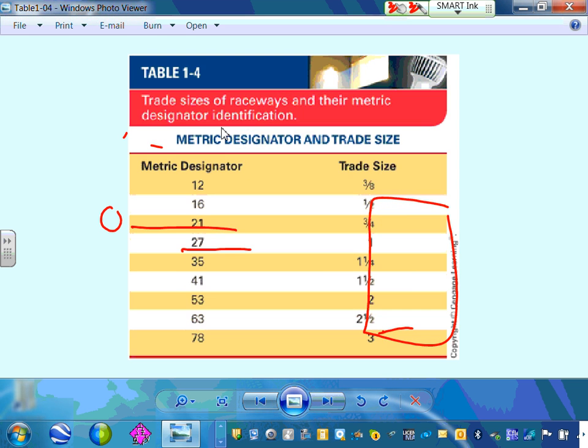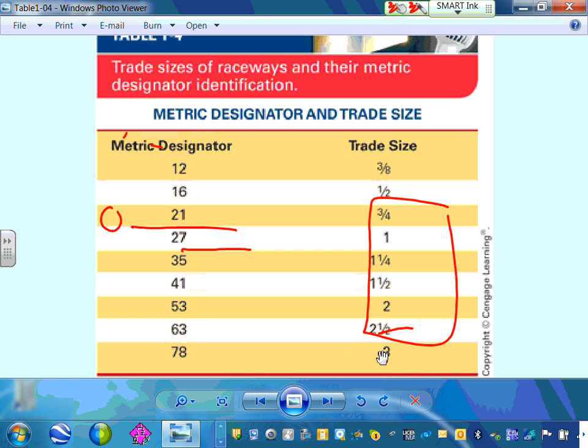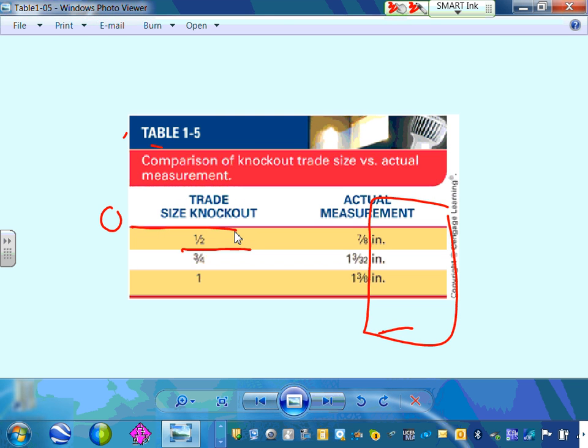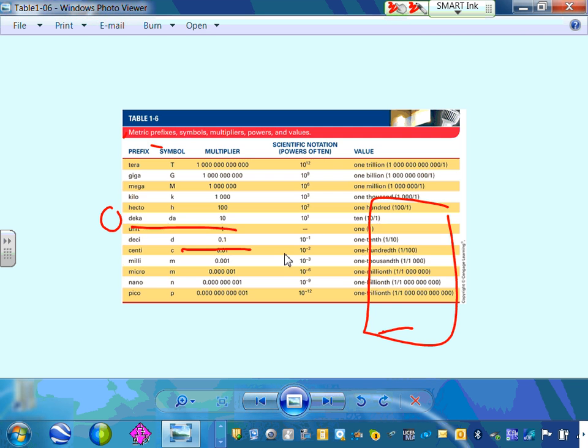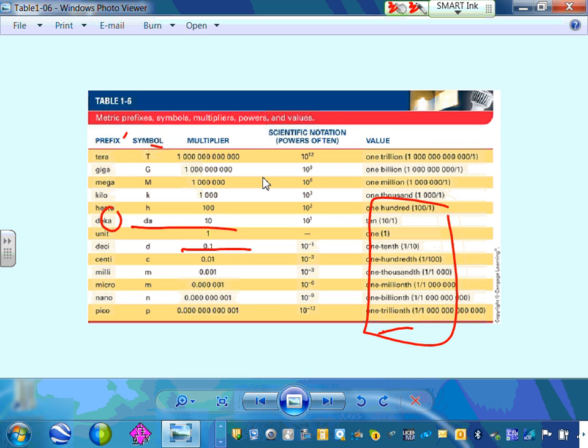Here's metric designator versus trade size. For example, 3 inch is equivalent to about 78 millimeters. These are different trade sizes — the actual size for the trade size knockout tool is different. So when they say half an inch EMT, if you measure the interior diameter, you'll find it's different from half an inch.